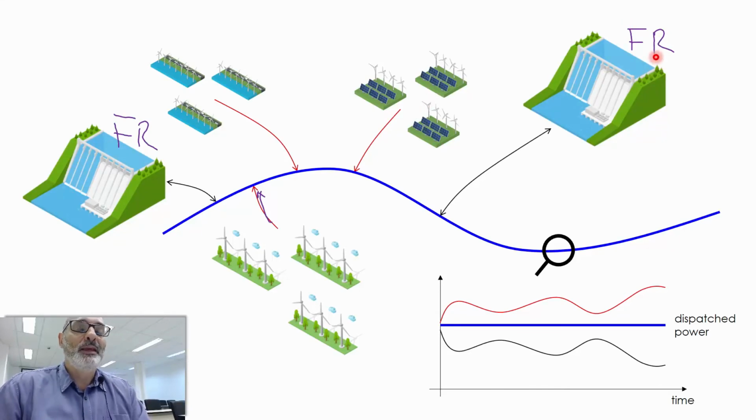So what I call functionality of the reservoir is becoming increasingly important in a scenario in which you have several sources of intermittent performance. The point is not to generate a lot of electricity. I showed you, we made calculations that the potential for growth in terms of generation is very limited for hydropower. But in my opinion, the role they are going to play is not in terms of supplying power to the system, but in terms of compensating the fluctuations of these intermittent sources. That is a very important role, because you have very few systems that are able to cope with this task, because the quantities are very high.